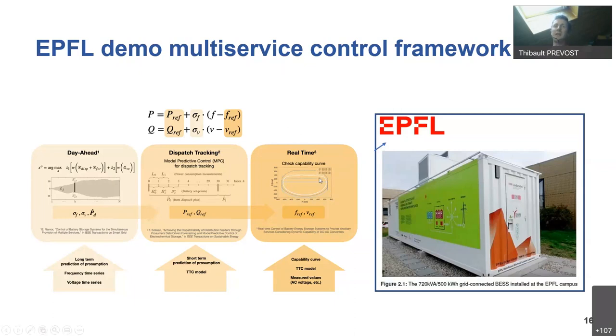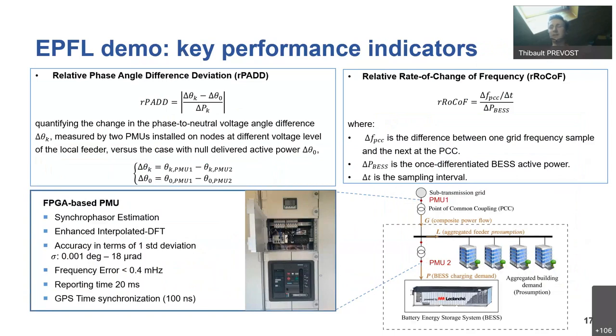Eventually, they developed some kind of capability check of the curve, because it's very easy to limit P and Q when you are grid following, but when you are in grid forming, it's a bit more tricky. So they ensure that they do not risk hitting the limit every cycle and changing the set point. Then they add on top of this control different services. For example, they have a dispatch tracking that they do every hour to change the PREF and QREF depending on the needs and depending on the consumption that was on the university feeder. And they also have a day ahead forecast so they can plan that they will have enough energy available to deliver the service all around the day. So it is very interesting to see that the grid forming can be put into an existing storage and deliver all the services that were delivered before this grid forming.